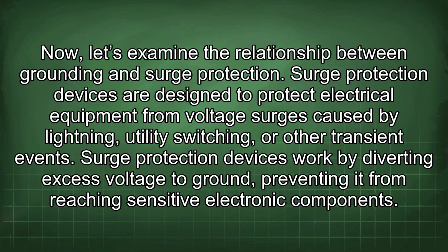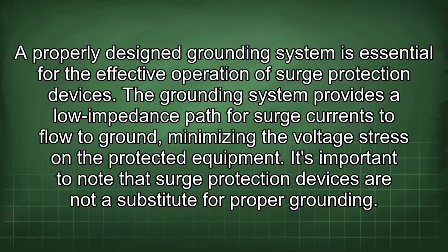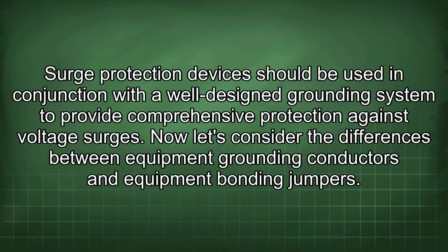Surge protection devices are designed to protect electrical equipment from voltage surges caused by lightning, utility switching, or other transient events. Surge protection devices work by diverting excess voltage to ground, preventing it from reaching sensitive electronic components. A properly designed grounding system is essential for the effective operation of surge protection devices. The grounding system provides a low impedance path for surge currents to flow to ground, minimizing the voltage stress on the protected equipment. It's important to note that surge protection devices are not a substitute for proper grounding. Surge protection devices should be used in conjunction with a well-designed grounding system to provide comprehensive protection against voltage surges.